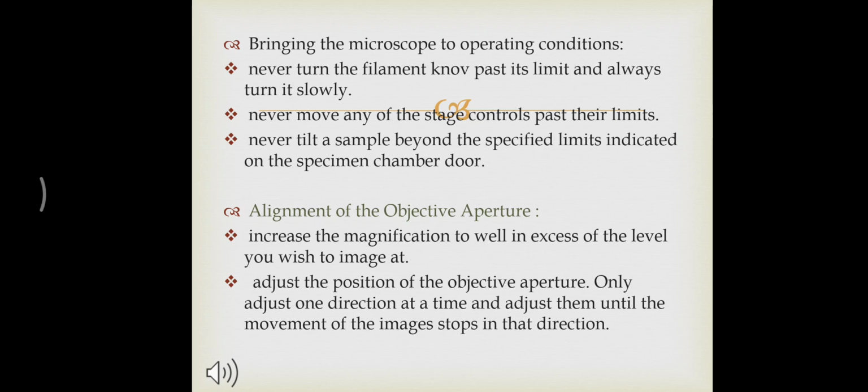Third, bringing the microscope to operating conditions. Never turn the filament knob past its limit and always turn it slowly. Never move any of the stage controls past their limits. Never tilt a sample beyond the specified limits indicated on the specimen chamber door.